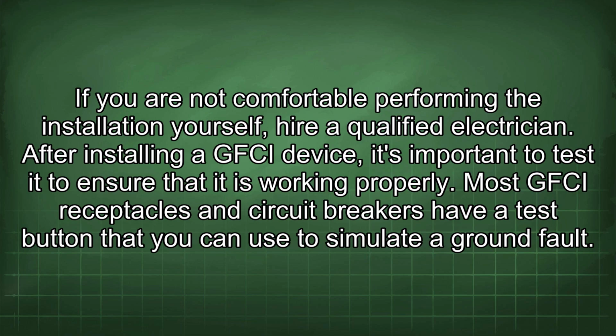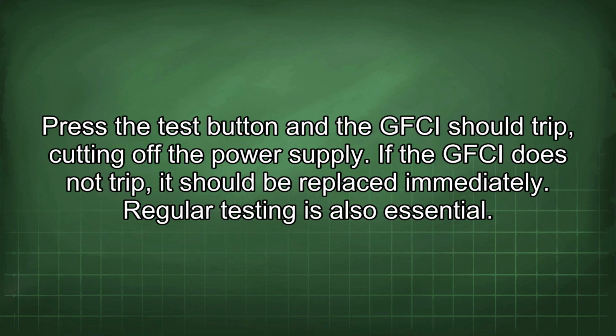After installing a GFCI device, it's important to test it to ensure that it is working properly. Most GFCI receptacles and circuit breakers have a test button that you can use to simulate a ground fault. Press the test button and the GFCI should trip, cutting off the power supply. If the GFCI does not trip, it should be replaced immediately.